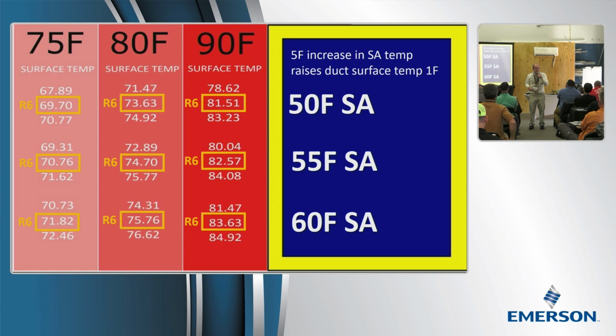Now what's he going to do? Right? He's there on a service call, so he doesn't get to do some of the other things that we'll talk about, because it's just not in the scope of a service call. And look what's happening here. 90 degrees. Look at these dew points. These are the surface temperatures of the duct. It's in the 80s. That's pretty safe, even in climate zone 1. So as a general rule, I say that if the air around the duct is 90 degrees or more, it shouldn't be sweating, because the dew point would have to be in the 80s.